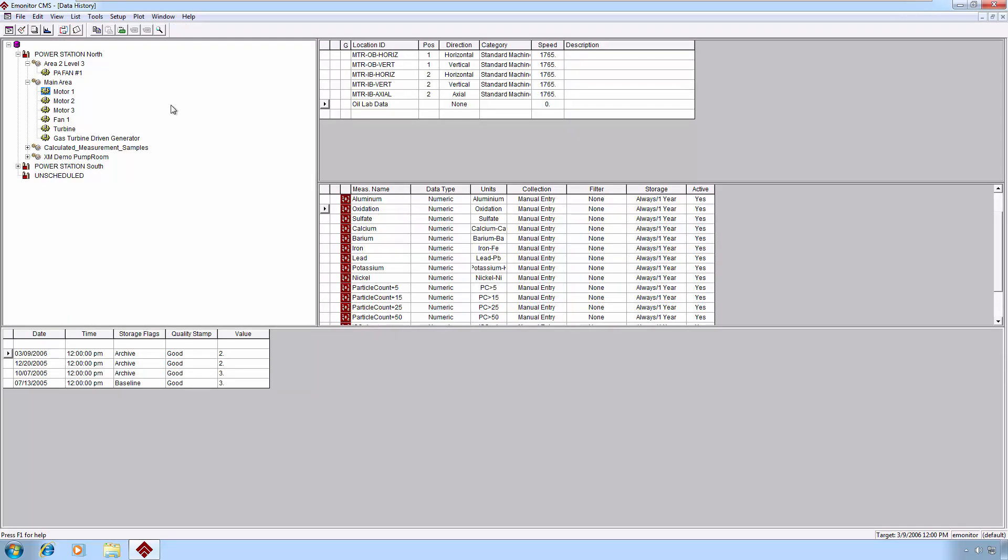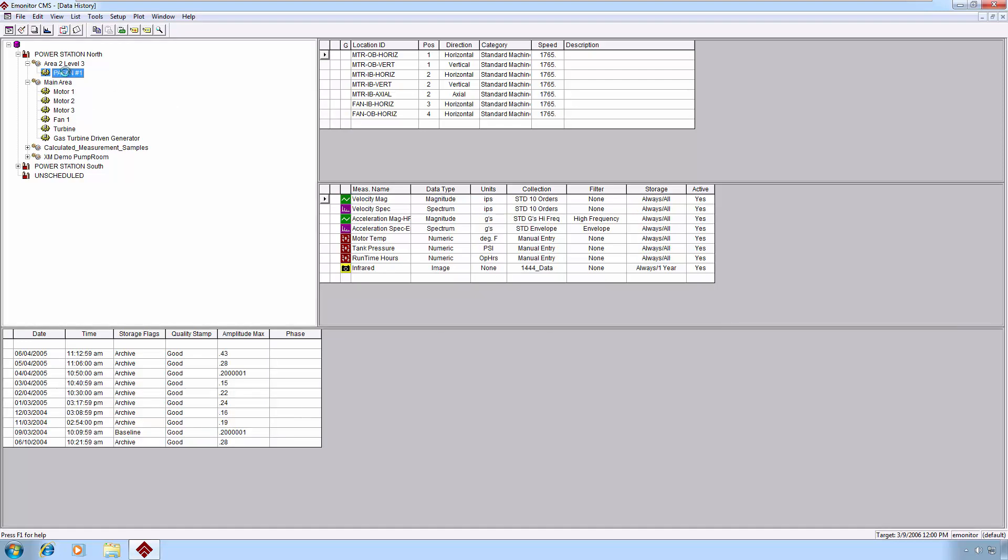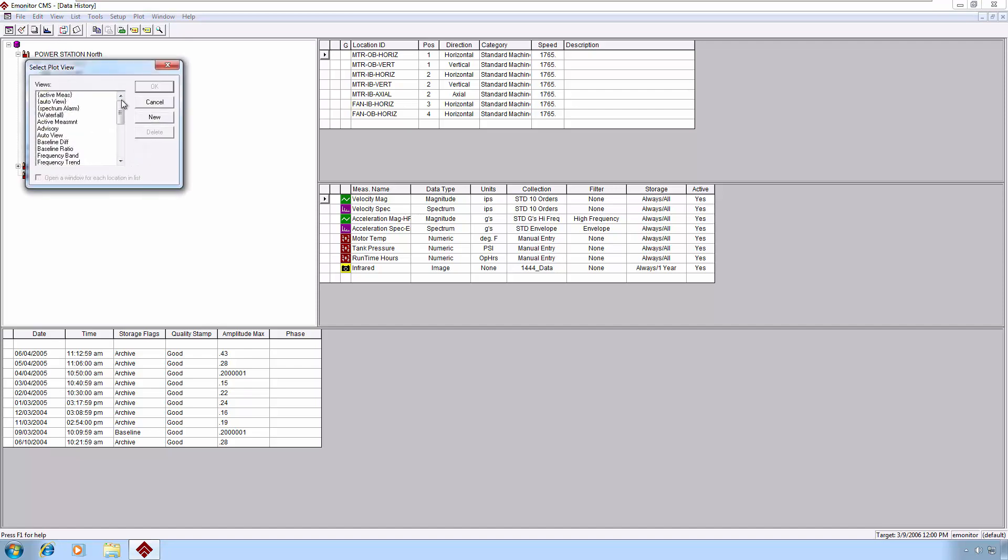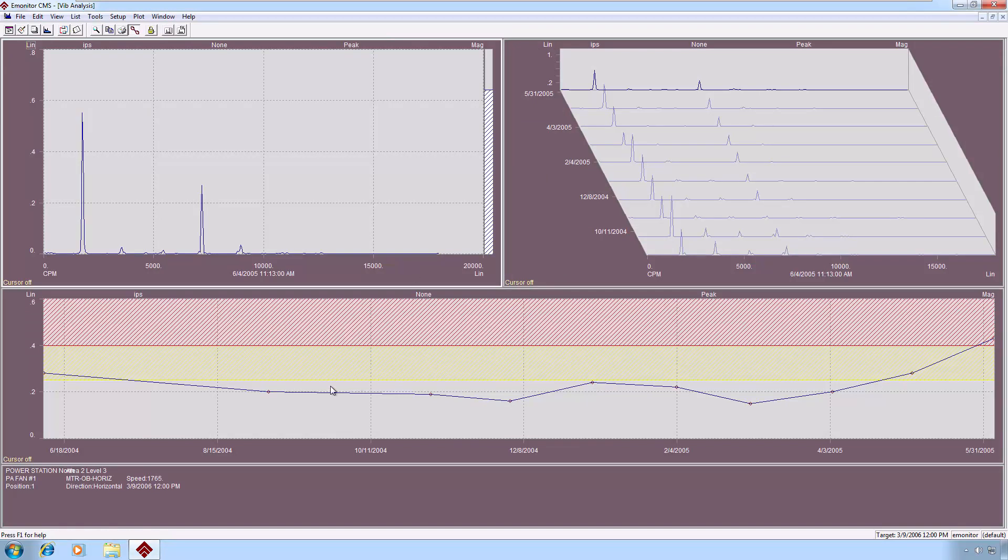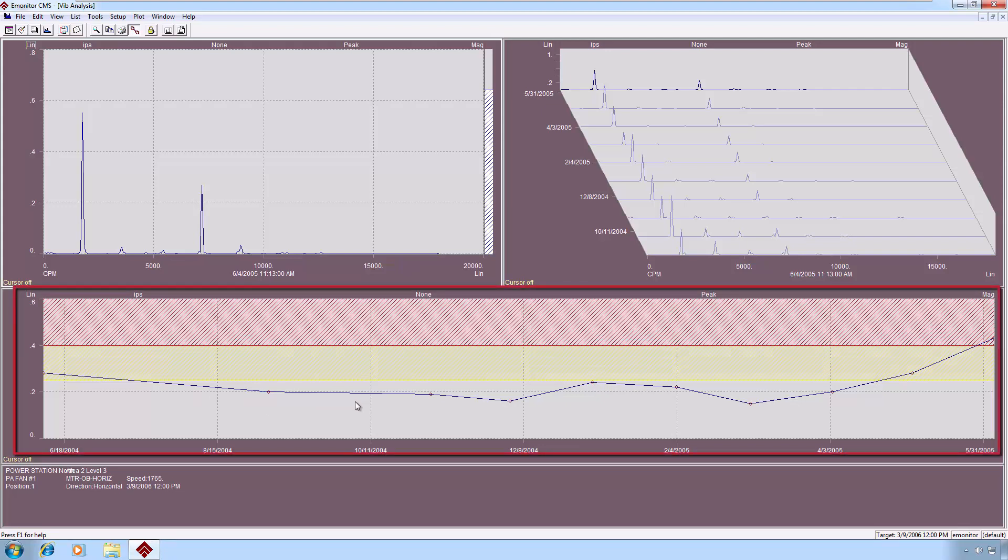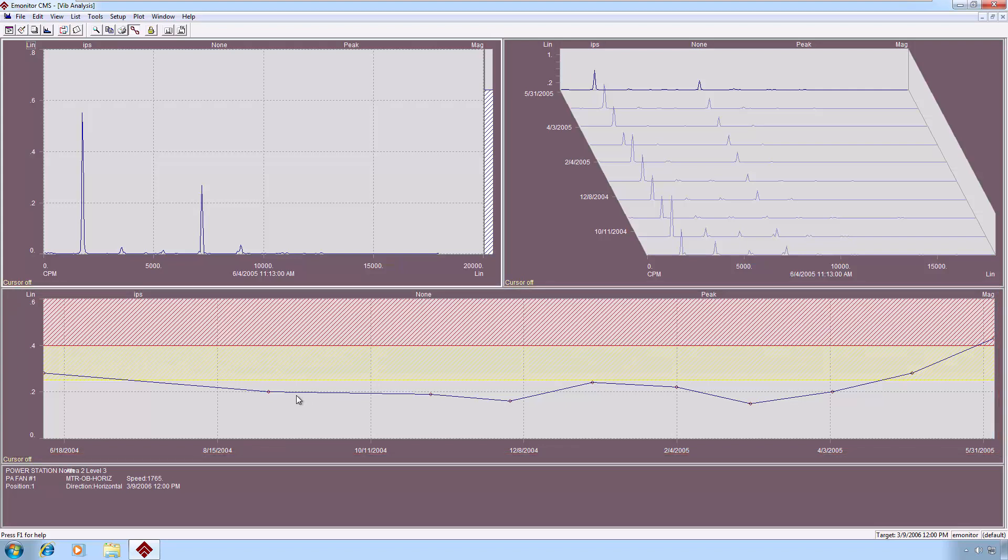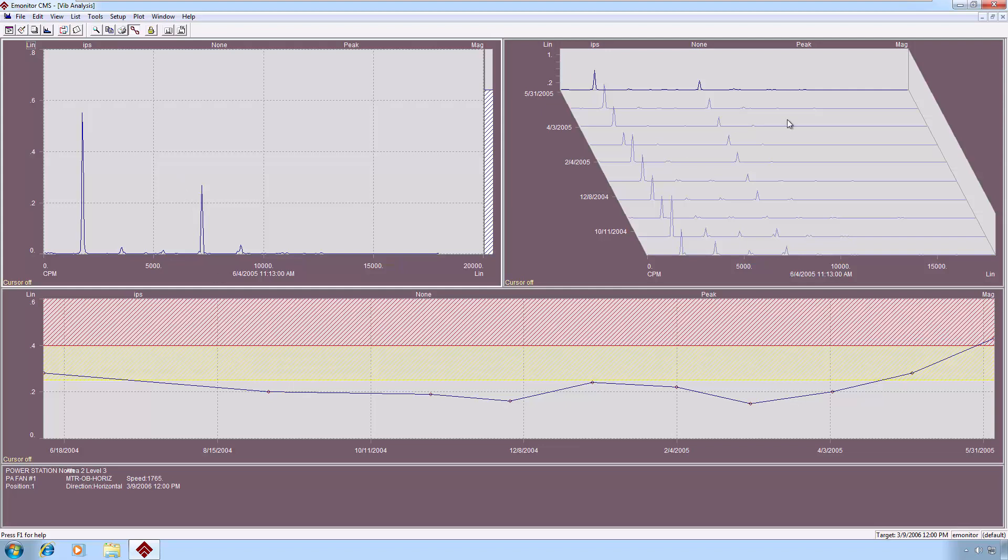Let's take a look at one last view. We'll go back to our PA fan data again. Probably one of our most popular vibration analysis views is called, coincidentally, VIB analysis. And it'll look very similar to the frequency trend plot. The big difference is that instead of a dynamically defined frequency band trend at the bottom, this is actually our overall. So this is somewhat similar to our trend and spectrum, except instead of just the trend and the spectrum, we're getting the trend, spectrum, and waterfall.